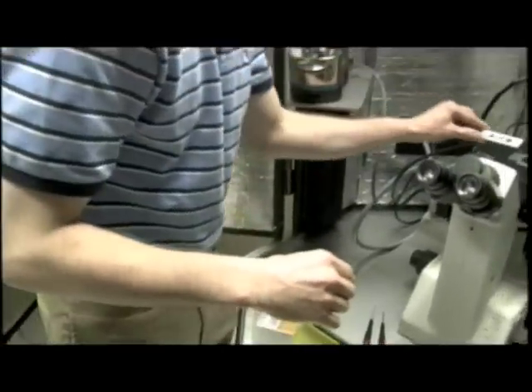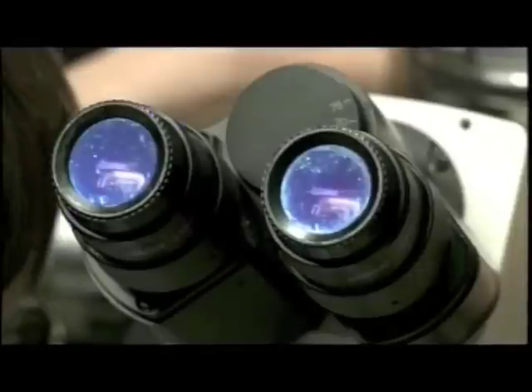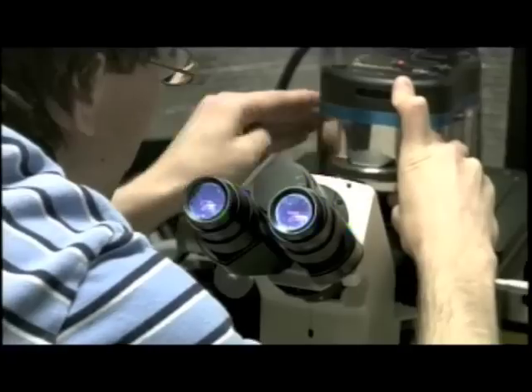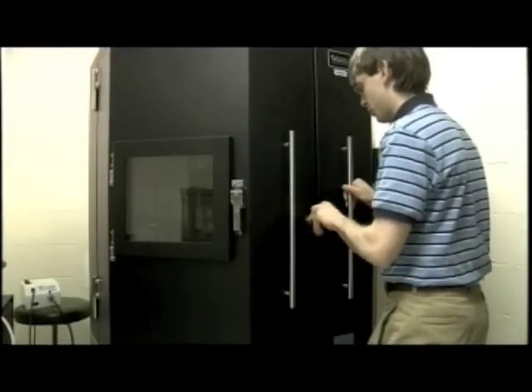As part of his MD-PhD studies, Dominic uses Northwestern's Atomic Force Microscope to figure out which surfaces in the body might support a mussel-inspired adhesive. The Atomic Force Microscope works by feeling a surface. You shine a laser down onto the probe, which is something like your finger, and you look at how, as your finger gets bent going over higher surface features, the laser reflection angle will change — and we're able to detect that.